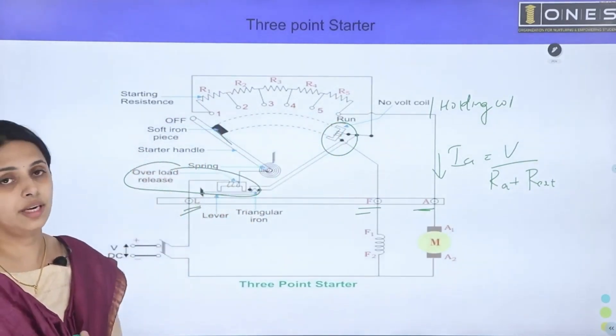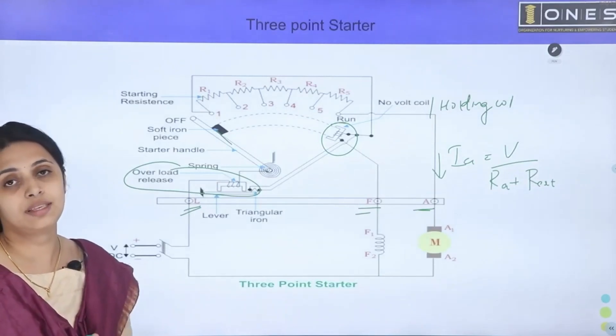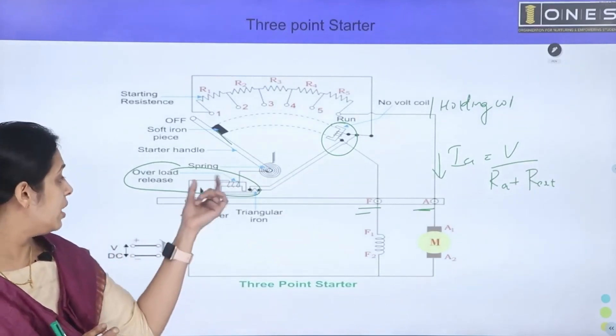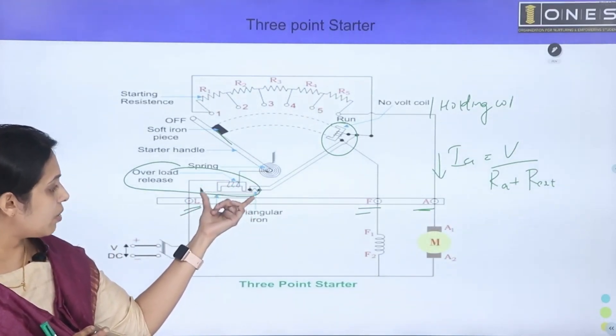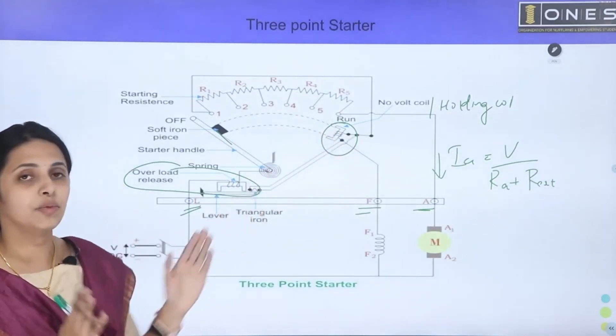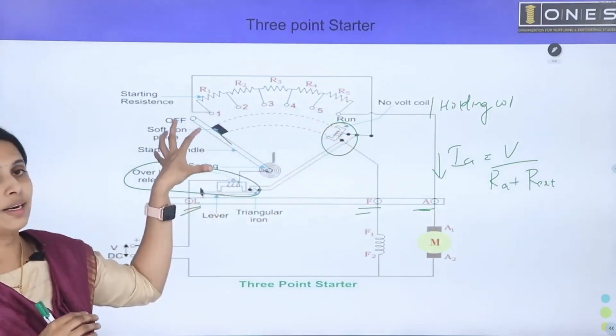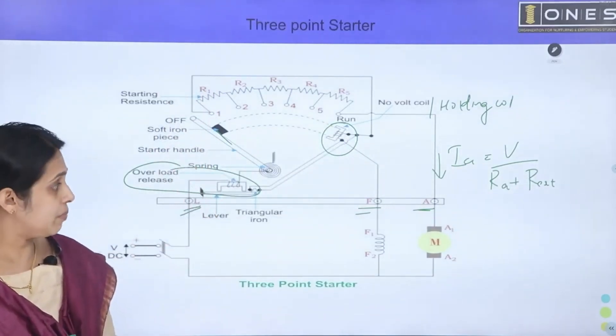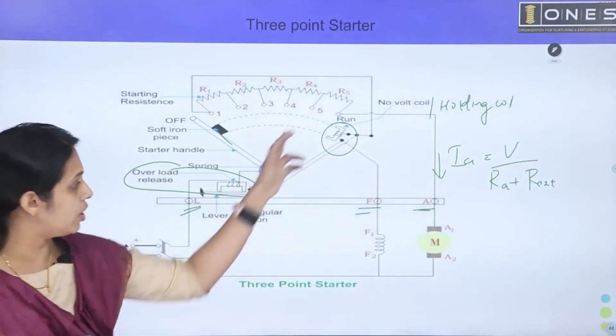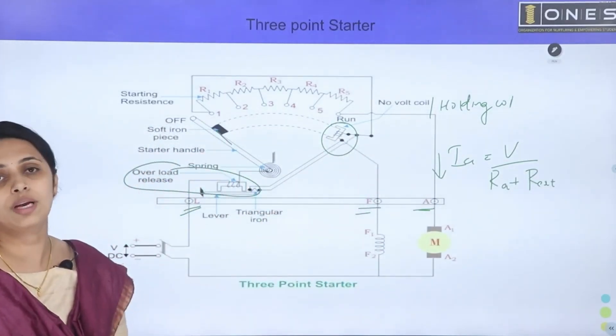The overload release protects against excessive current. If overload occurs, the release coil pulls the starter arm back to the initial position. The holding coil is connected in series with the field circuit. This is the basic operating principle of the 3-point starter.